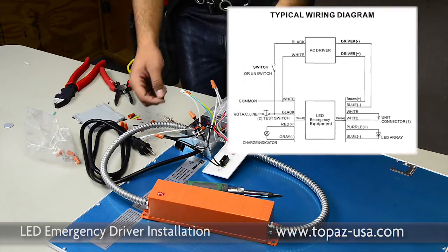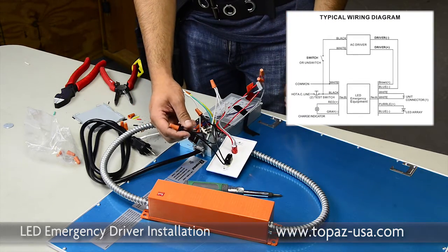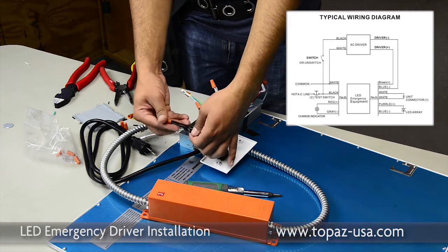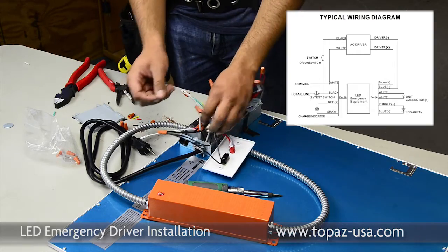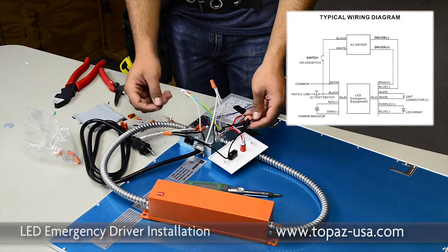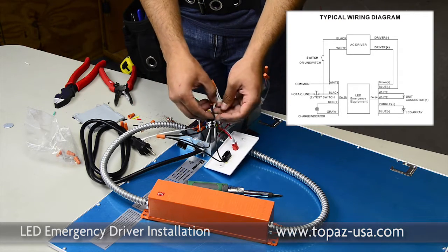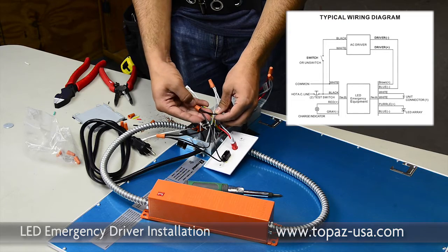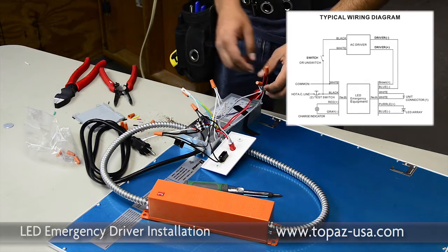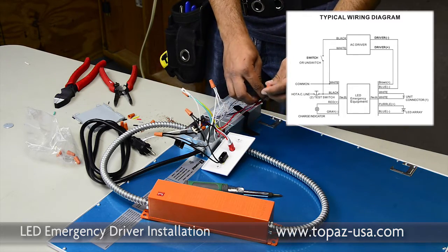Here's an overview of what we've completed. On the test switch, we have the power supply coming in — three conductors: the feed coming in, the power lead that goes to the emergency ballast, and the lead that goes to the actual switch. The second lead for the switch leg is wired directly to the LED array. The indicator light is wired gray to gray, red to red.